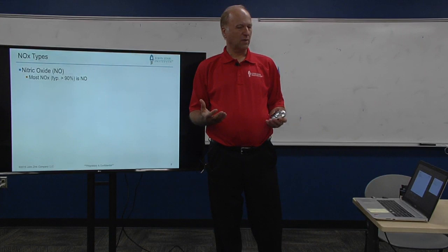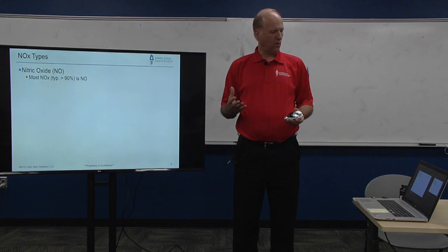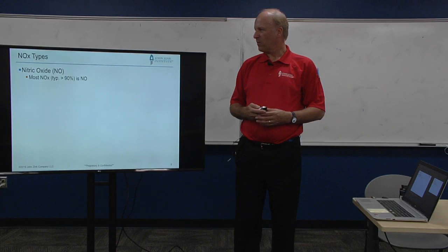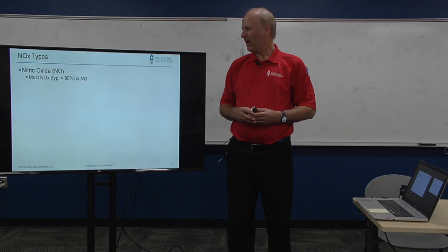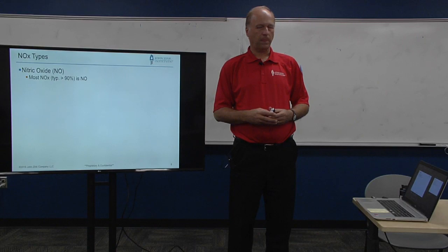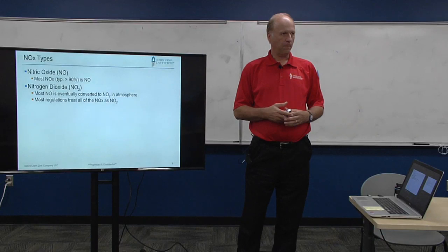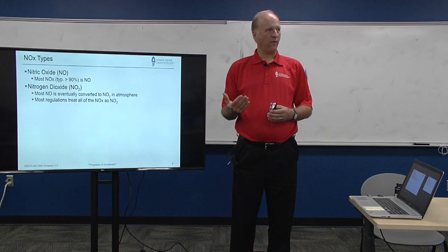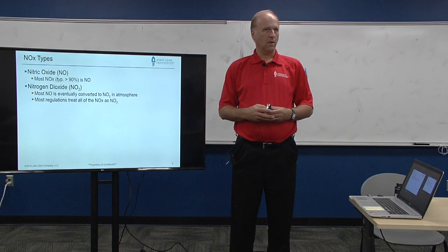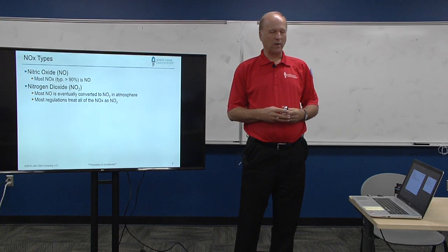There are multiple forms of NOx but in combustion there are really only two that are important. The most important one is nitric oxide, or NO. In most process heaters, about 90% of what comes out of the stack is in the form of NO. The second important one is nitrogen dioxide, NO2, which is usually only on the order of 5 to 10% of the NOx generated. But this one's important because regulations often require you to report all of your NOx as NO2. The reason is that NO, when it gets into the environment after a few days, normally converts to NO2.